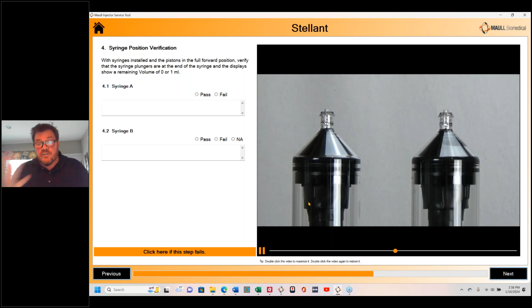So the next screen is actually going to show it. We're going to put the syringes back on. Like I said, we leave nothing to chance. Put the pistons on and then drive the pistons all the way forward. Now, plunger position verification. This is a test. We're just going to make sure that the syringe volume is accurate. If my display says there's 50 milliliters of fluid in the syringe, there's 50 milliliters of fluid in the syringe. And this is the actual procedure that it goes through. So we'll just put pass, fail, or NA on syringe B, because if this were a single head syringe, there wouldn't be a syringe B. So if this were a single head syringe, you would select NA right there.